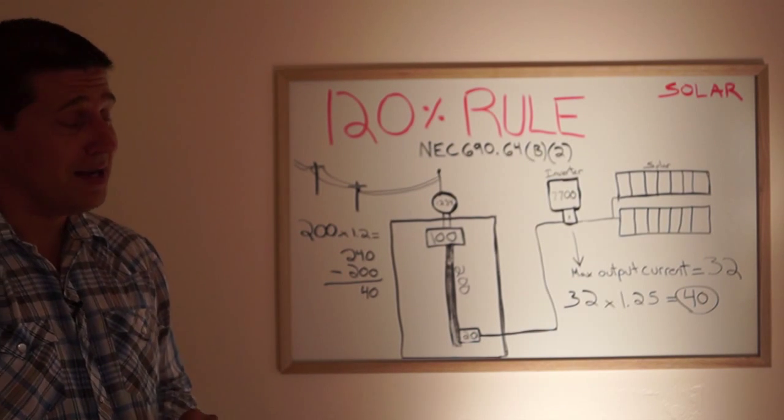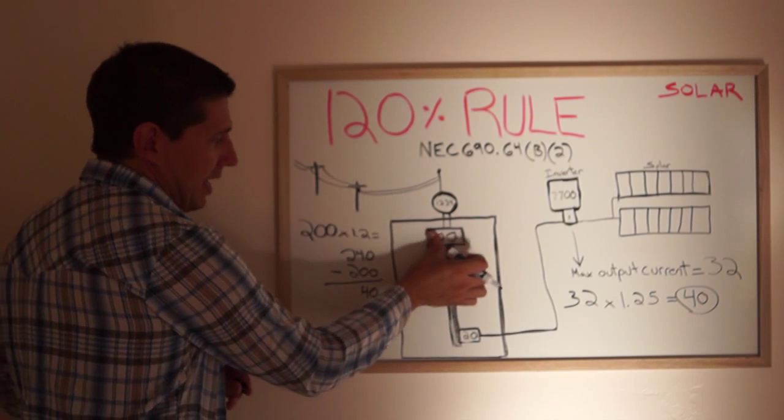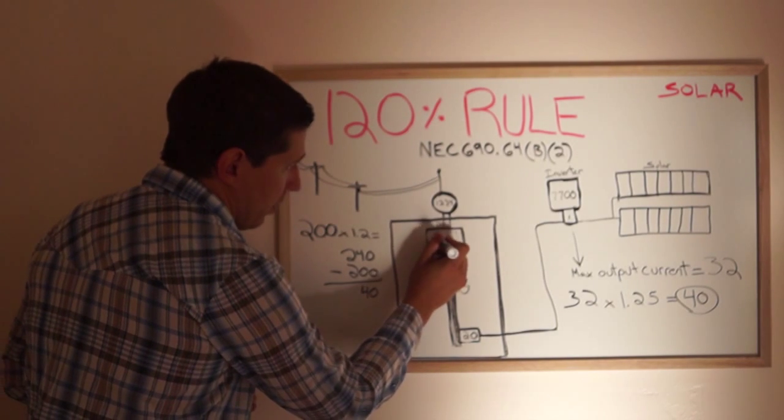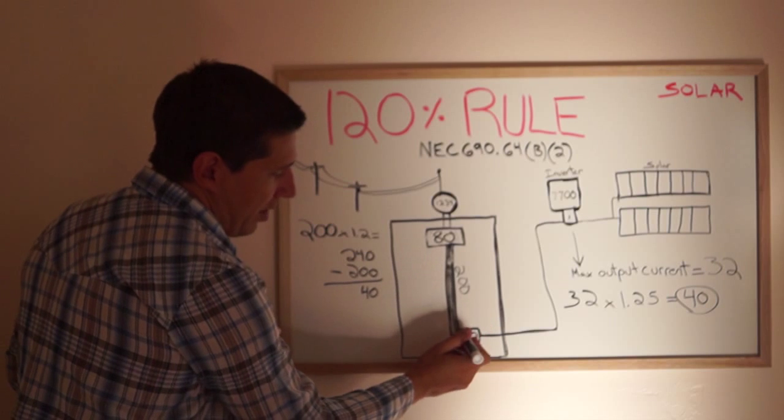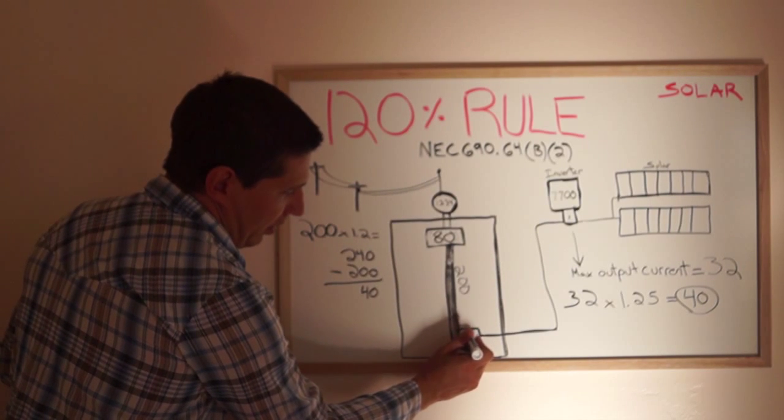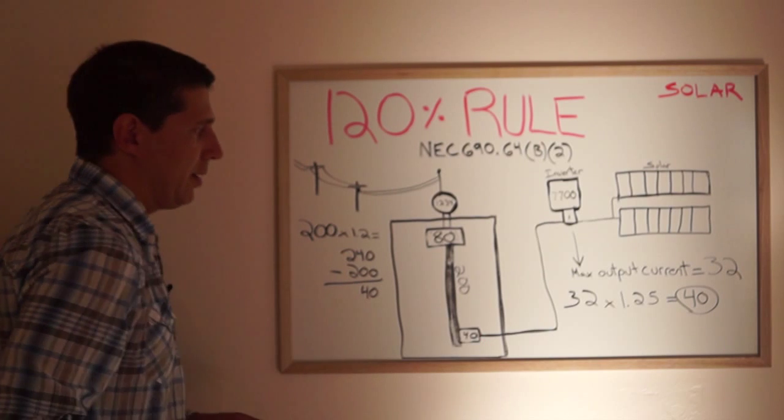Now you can derate as well here. We can derate this to 80 amps, assuming there's load calcs performed, which would allow you to install your 7700 watt inverter on a 100 amp panel.